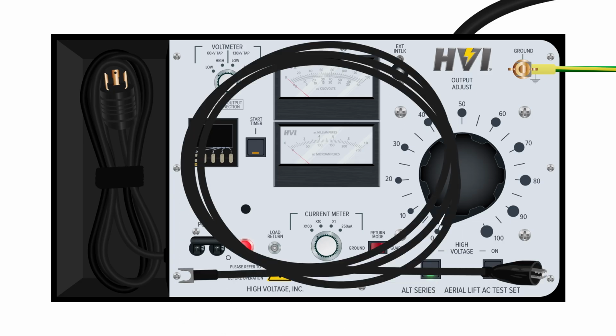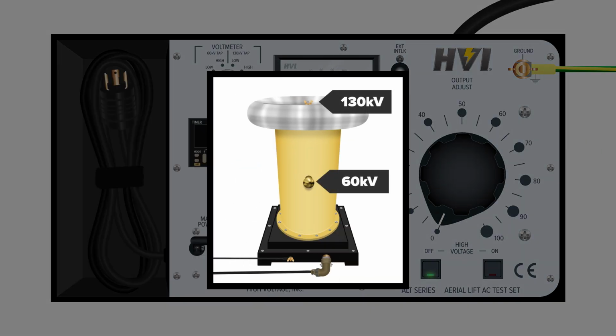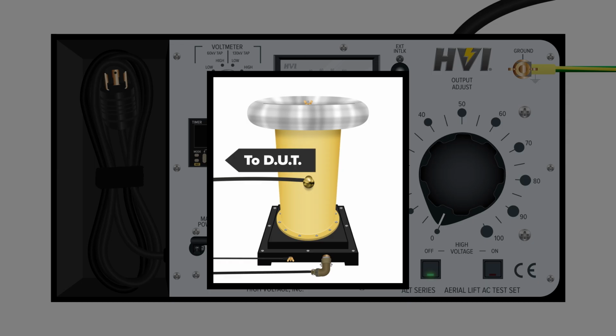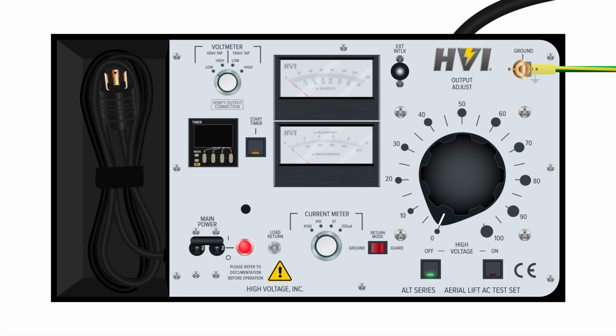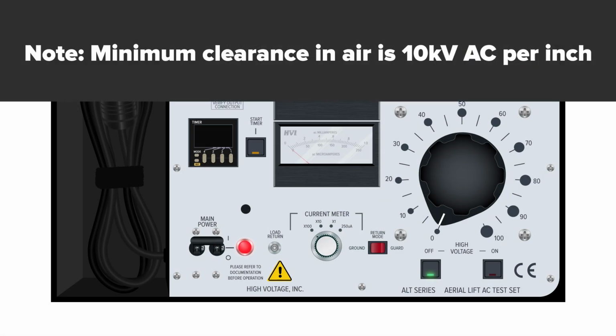At this point, choose which output tap you will use to connect to the DUT, as well as a suitable connection lead. This connection lead is customer supplied. Refer to the user manual for further information and recommendations on choosing a connection lead. Secure the high-voltage connection lead to the high side of the DUT, making sure that there is enough clearance to grounded objects for the supplied test voltage.